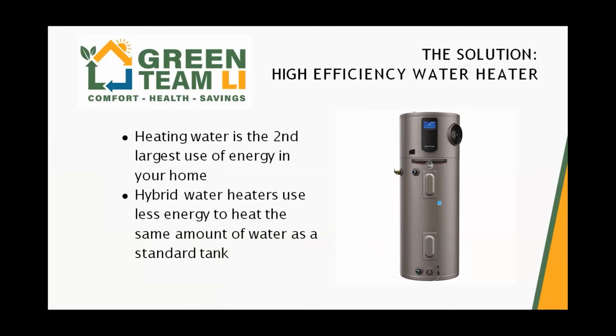And so what it's doing, you think about the normal philosophy of heating. We either combust a gas, we combust something, and we're looking to transfer the heat from that combustion into our water. And if we design it really, really well, we might get that to 95% of the heat from that combustion going into our water, and that's pretty close to the theoretical limit. And some of the older systems are 50%. Only 50% of the heat is getting transferred into the water.